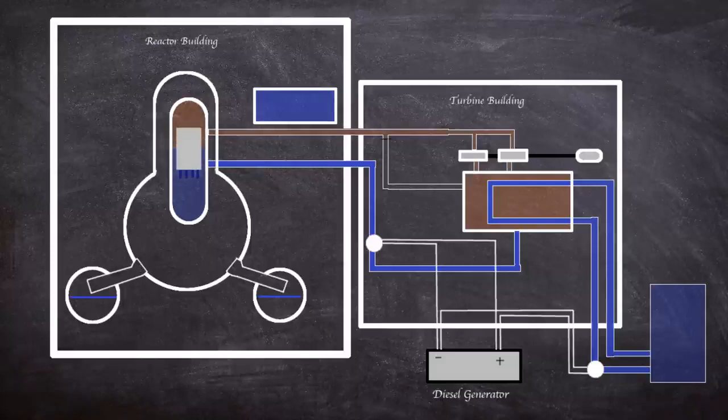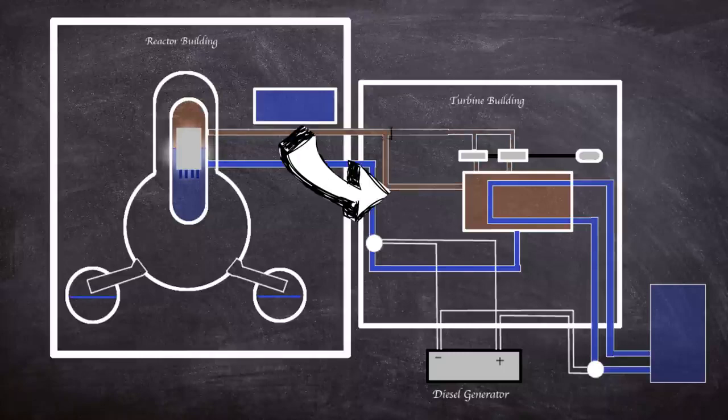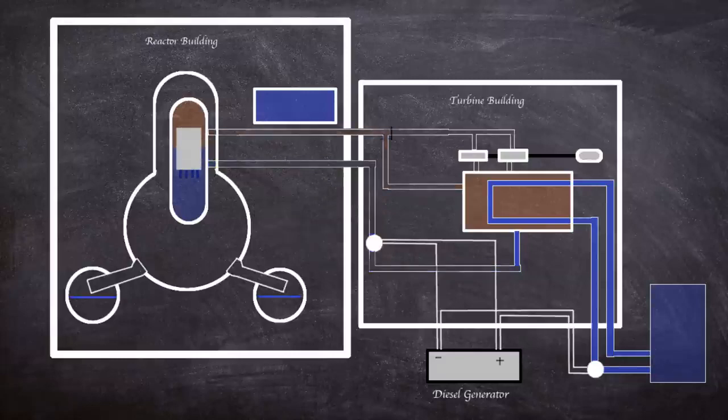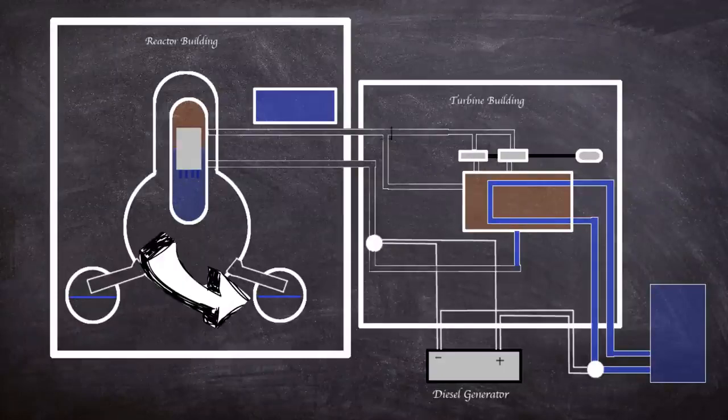To help with cooling, in normal shutdown the turbines are bypassed and coolant steam goes straight to condensers, then is pumped back to the core. However, during this event, the reactor was completely isolated from the turbine building due to power loss. With the usual cooling isolated, a backup system using the suppression pool was used.